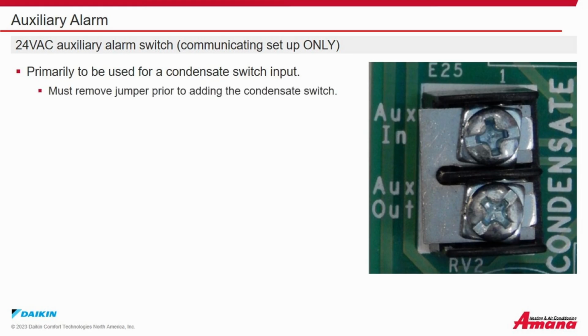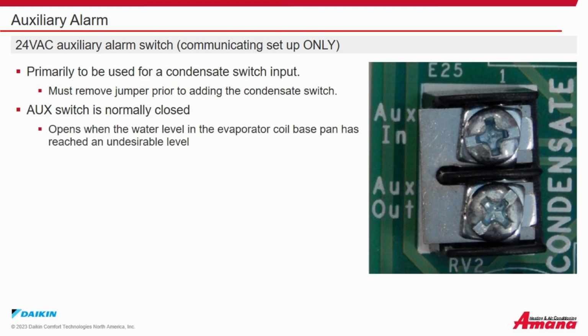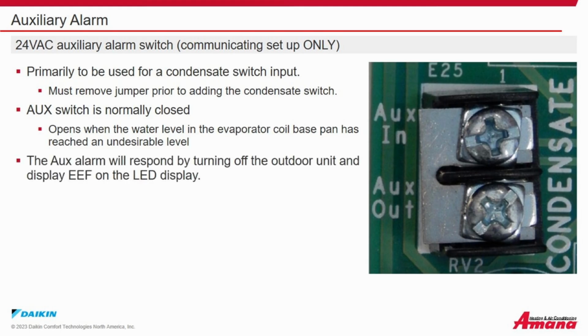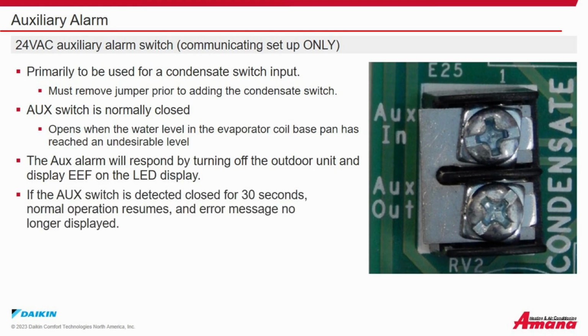You must remove the jumper before adding the condensate switch. Auxiliary switch is normally closed. The switch opens when the water level in the evaporator coil base pan has reached an undesirable level. The auxiliary alarm will respond by turning off the outdoor unit and displaying EEF on the LED display.